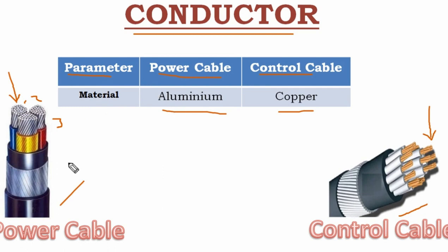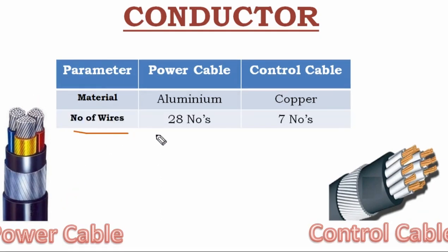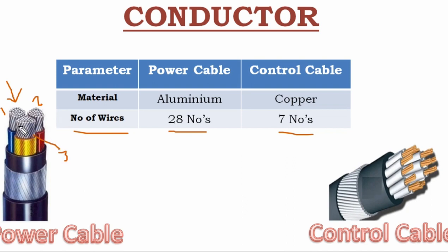Now we discuss the second parameter — the number of wires. In the power cable, the number of wires is 28 per core, and in the control cable it is 7 per core. The power cable has three cores, and each core has an aluminum conductor made up of 28 individual strands. The control cable consists of 16 cores, and each core consists of 7 strands of copper wire.